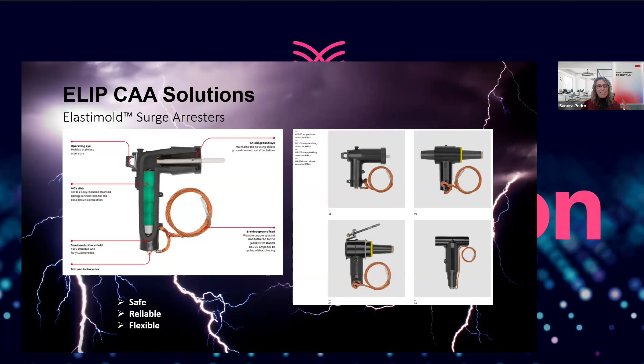But there's an added benefit to this surge arrestor. With that capability of offloading energy, when there's an overcharge into a transformer, which are typically oil filled, or a piece of switchgear, that capital equipment gets loaded and gets hot, and quite often the potential of a fire becomes a problem. If you have an oil fire in a grassy area, it can spread through a neighborhood, into houses, and that would be devastating. So that's just an added benefit from our surge arresting capabilities, not only protecting the assets but protecting the environment around it as well.